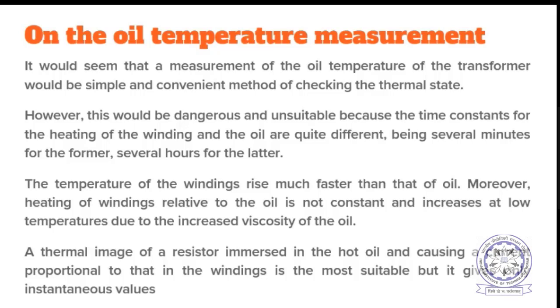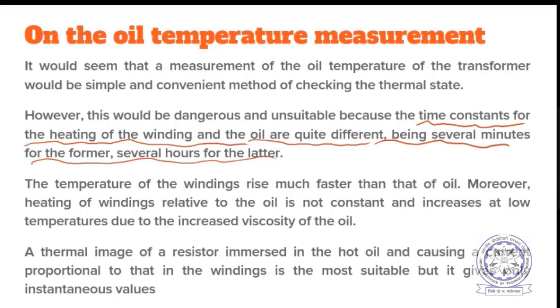However, this would be dangerous and also unsuitable, because there is a difference in the time constants of winding and oil. Which will be faster in temperature rise, winding or oil? The winding temperature will rise much faster and the oil temperature will rise very slowly, because it may take several hours in the case of oil, but the winding temperature may rise in minutes. So a measurement of oil temperature will not give you an exact idea of what is happening in the windings.